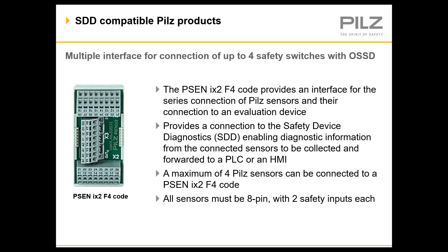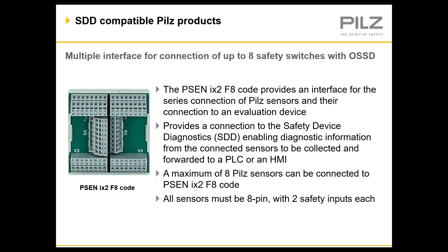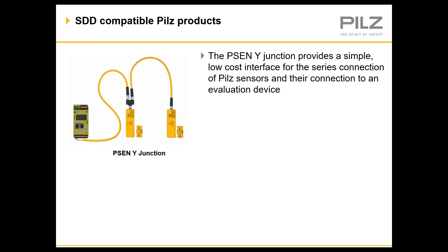While the majority of SDD systems utilize M12 quick-connect cabling, for situations where you need to hardwire either Pilz or third-party sensors, Pilz offers the PSEN IX2 family of interfaces. The PSEN IX2-F4 is shown here, which can connect up to four sensors, and there is also the PSEN IX2-F8, which can accommodate up to eight eight-wire sensors. Most systems, however, will use the low-cost IP67 Y-junction connector connected to a slimline coded switch. Used with a low-cost PNOZ s relay, the result is the most economical diagnostic system available in the marketplace.